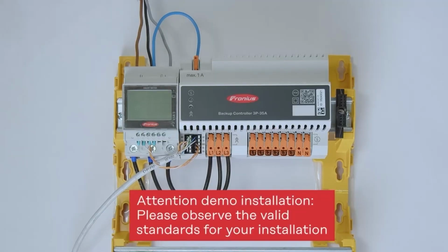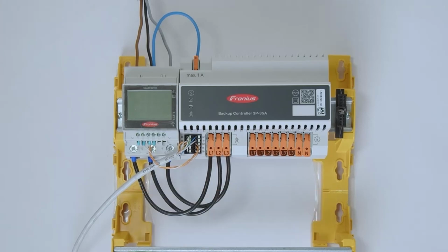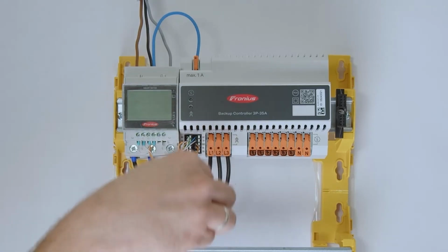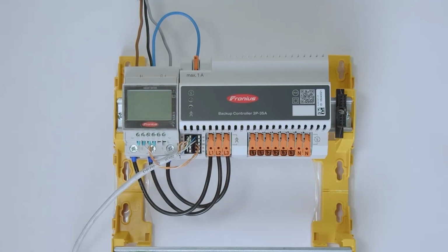So let's start with the cabling of the backup controller. Please note that we now have a demo installation, and of course in a real installation you need to watch all the national standards norms. So let's start on the top side of the Fronius smart meter. Here we go into the Fronius smart meter coming from the public grid, directly three-phase into the Fronius smart meter, and on the bottom we exit the Fronius smart meter and go directly into the backup controller.